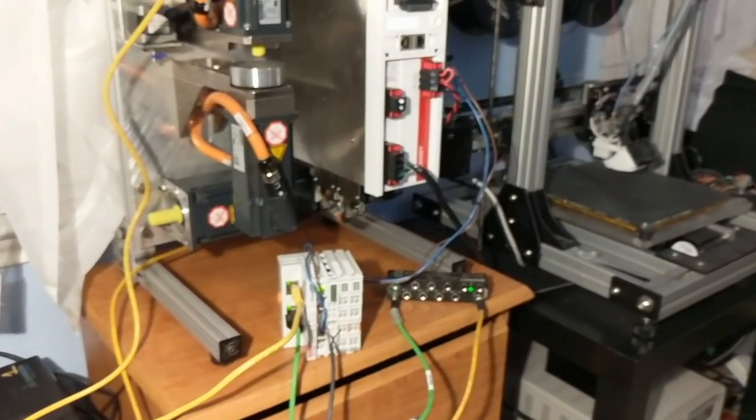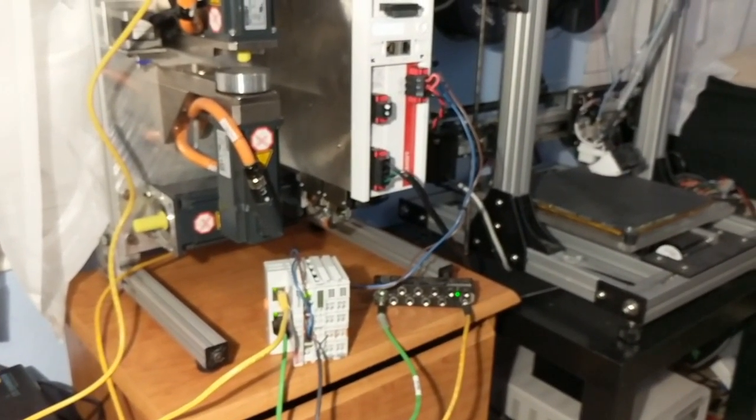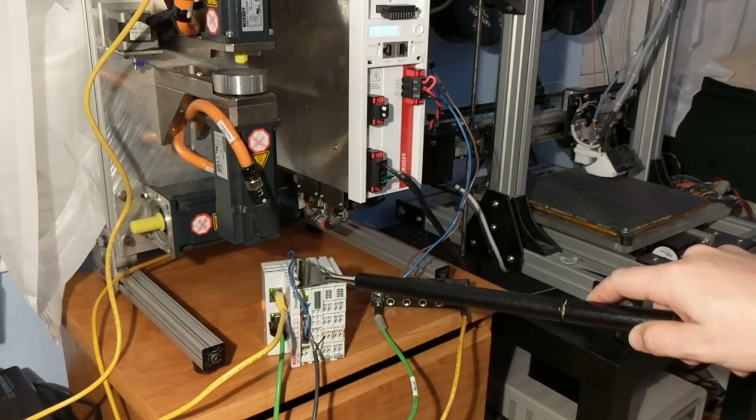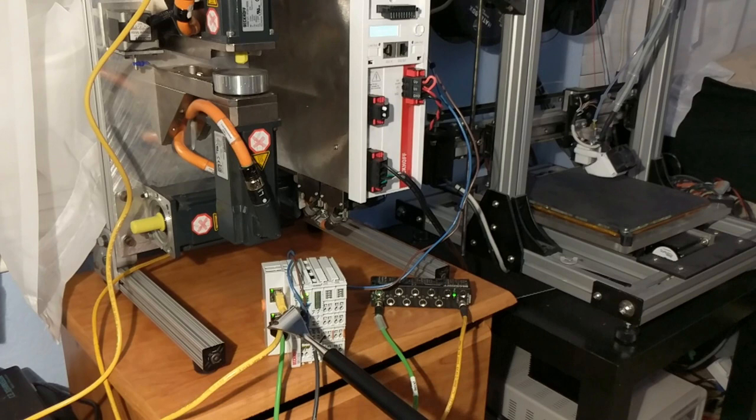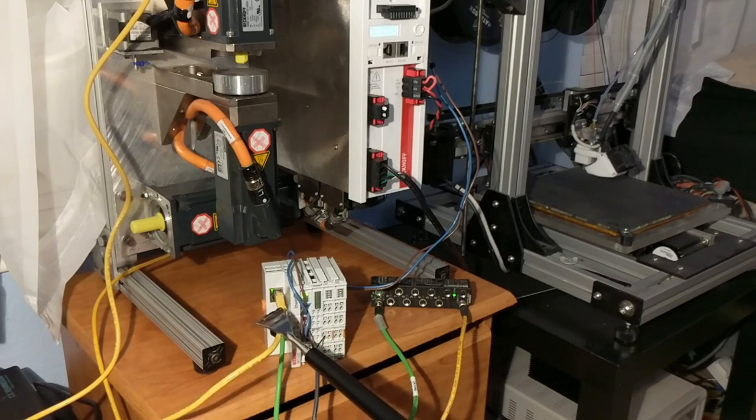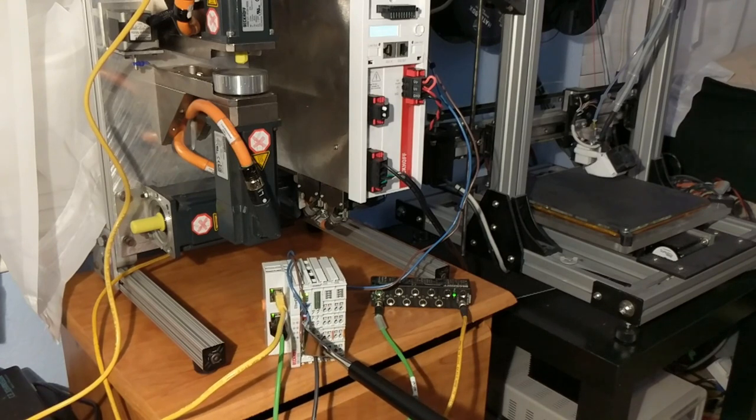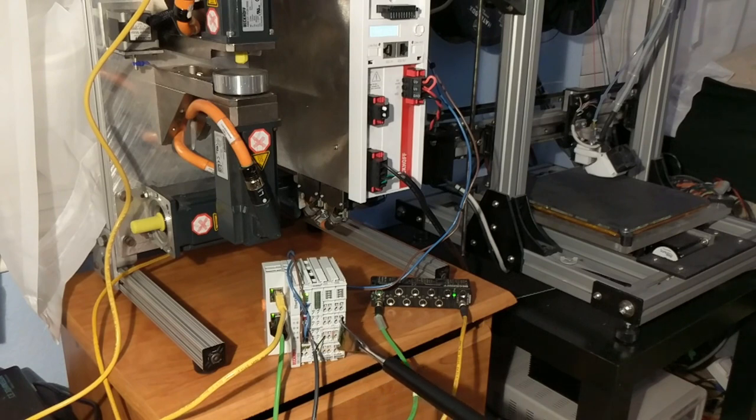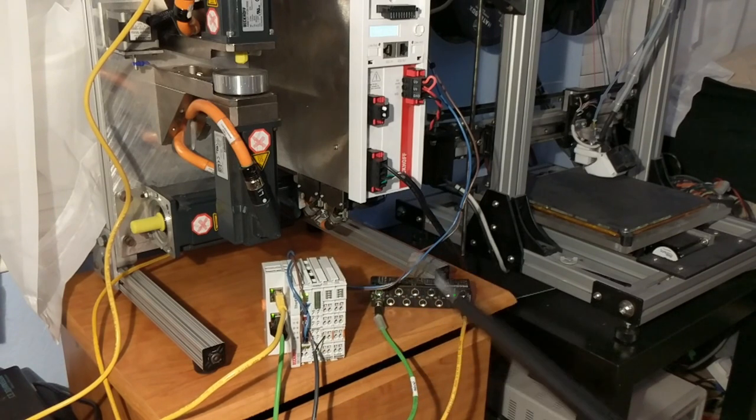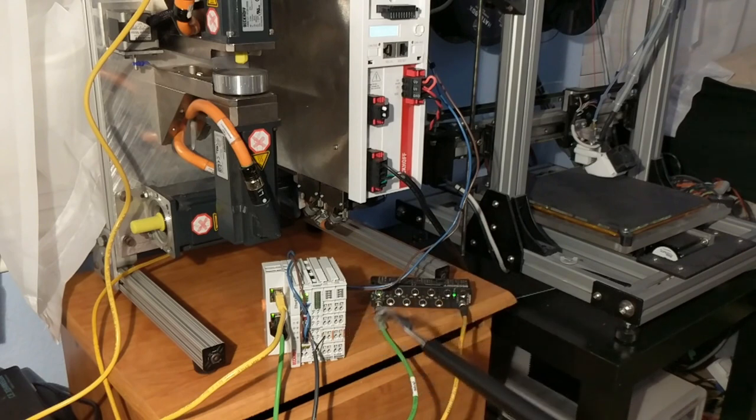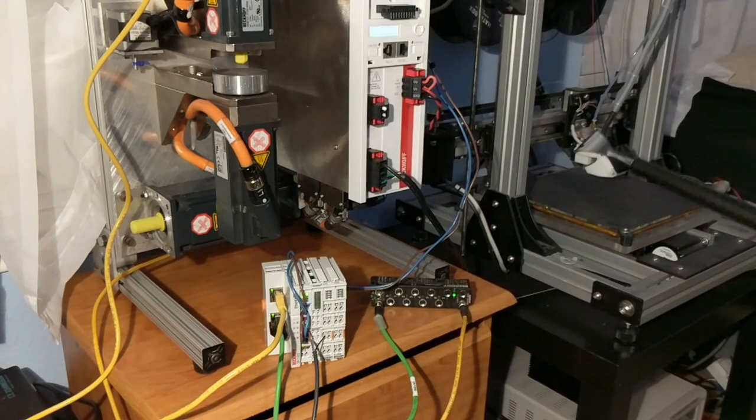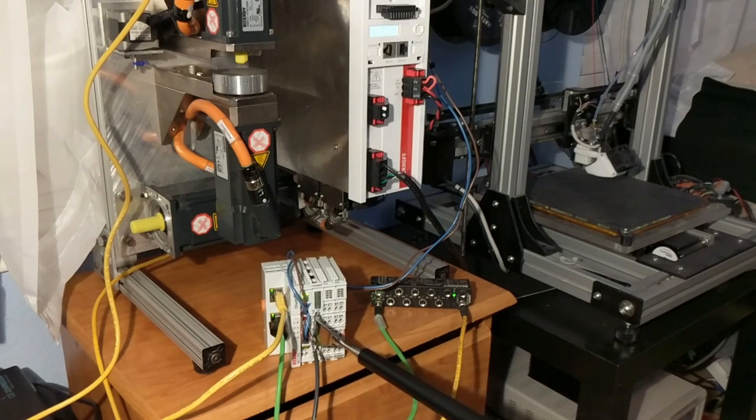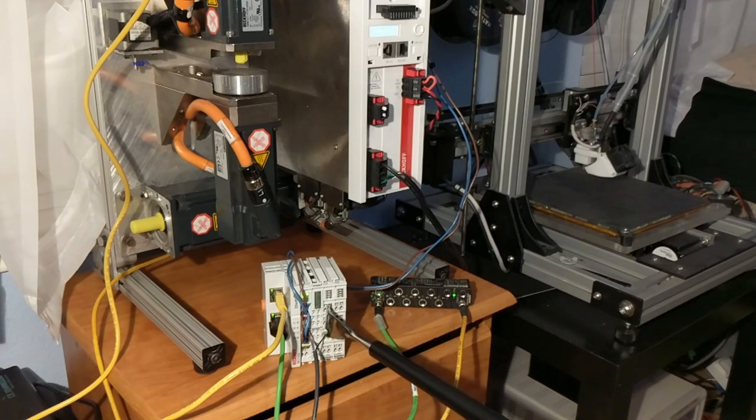So if you take a look down here, I've got my I.O. This bus coupler right here on the left side is an EK1100 and what that does is takes an EtherCAT RJ45 in, sends it back out, but in the middle here it puts all of your e-bus slices as well. So you could have these mounted in a remote box somewhere or just somewhere else in the cabinet if it doesn't make sense to put all these up here in the line. So what we've got here is like a potentiometer slice on the left there. We're not going to mess with that too much. An EL1008 and an EL2008.